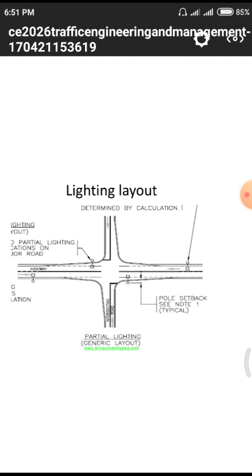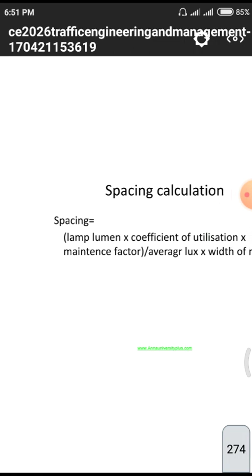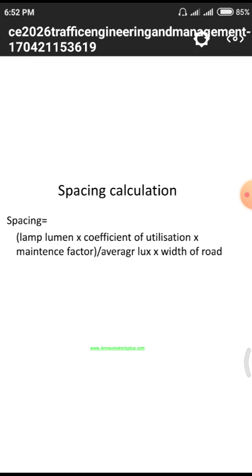It is the utilization curve. That means the distance of particular roads and utilized lines all over India. We have some quantity of utilization curves of these street lights. This is the formula for calculation of spacing between the two poles. Spacing equals lamp units, that means lumens or LUX, into coefficient of utilization into maintenance factor, divided by average LUX into width of the road. That is the formula for the calculation of spacing between light to light.